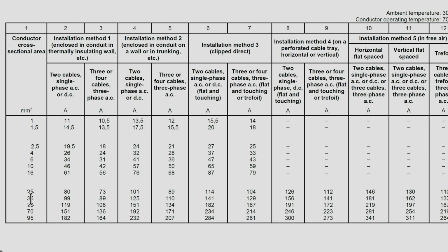I could even go as high as 25 millimeter, not because I'm worried about the current carrying capacity, but I would now have even a lower volt drop because there's a much bigger cross-sectional area on a thicker cable, which means that I will have a lower volt drop to the inverter. 16 millimeter for me would be the minimum in this application. Right, so now I'm going to install that.